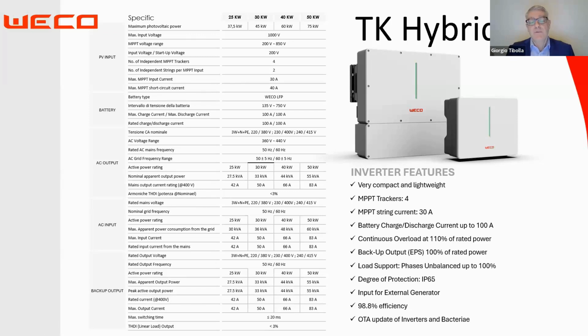to charge the battery with electricity from the network. The last way is when you want to do a retrofit. Retrofit means when you installed a solar panel, for example, 1 or 2 years ago, and now your client asks you to add batteries. In this case, you don't need to touch or modify the old string inverter, but only need to add this inverter that will manage the current and charge and discharge the batteries.